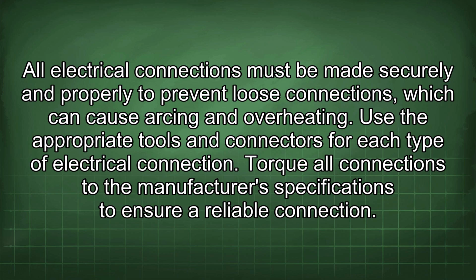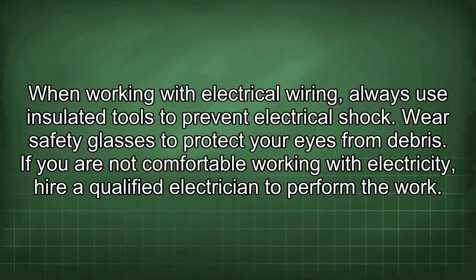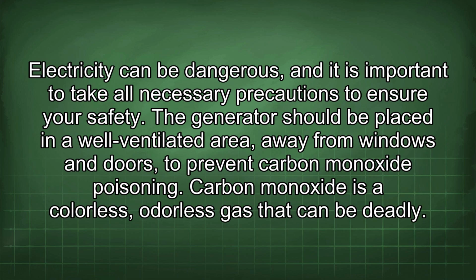All electrical connections must be made securely and properly to prevent loose connections, which can cause arcing and overheating. Use the appropriate tools and connectors for each type of electrical connection. Torque all connections to the manufacturer's specifications to ensure a reliable connection. When working with electrical wiring, always use insulated tools to prevent electrical shock. Wear safety glasses to protect your eyes from debris. If you are not comfortable working with electricity, hire a qualified electrician to perform the work. Electricity can be dangerous, and it is important to take all necessary precautions to ensure your safety.